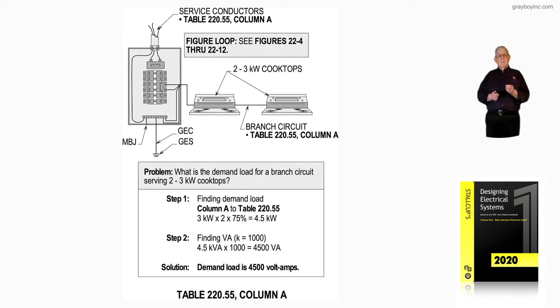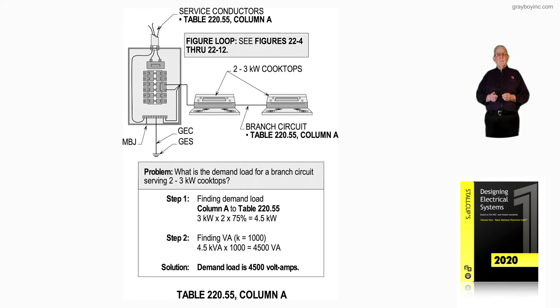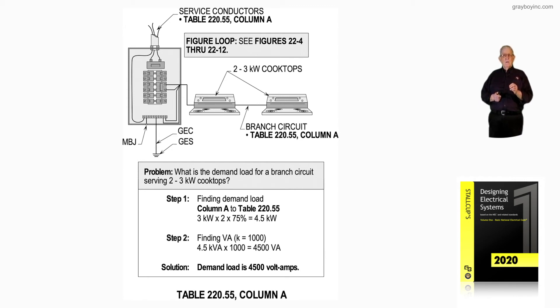You'd find diversity in the McGraw-Hill Electrical Engineering Handbook — those engineering handbooks would have that. In Step 1, we take the 3KW of each unit times 2 units, and from Column A, based upon these two units with their KW rating, we get a 75% demand. So instead of 6KW, we have 4.5KW for the service and for the branch circuit.